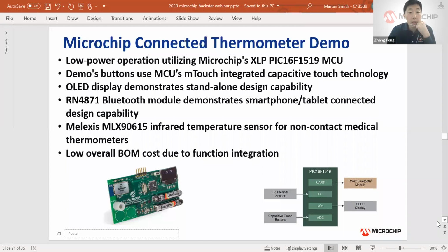So this demo uses an off-the-shelf third-party infrared temperature sensor, the MLX90615 from Melexis, and we're upgrading it to their newest temp sensor, the MLX90632. So according to the datasheet of Melexis' newest medical graded temp sensor MLX90632, its medical version is factory calibrated with an accuracy of plus or minus 0.2 degrees Celsius within the narrow object temperature range from 35 to 42 degrees Celsius for medical applications, with a resolution of 0.01 degrees C. So that's the accuracy this demo can achieve.